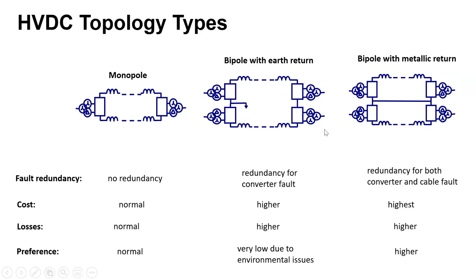If we now turn our attention to bipole topology, whether it's earth or metallic return, let's look at the one with metallic return. It has a sending end converter and a receiving end converter with three transmission lines connecting all four converters. If there is a fault in one of the sub converters, either in this converter or in this converter, or even in this transmission line, then only half of the loop will be lost, meaning half of the rated power can still be transmitted through this topology.